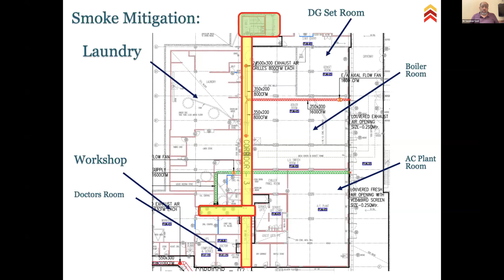Now, having said that, I will come back to the basement car park. So what we are talking about is smoke mitigation—please read this line. This is the line which helped me present to my committee: any kind of smoke mitigation system has to function in terms of ACPH when the fire is extinguished. The pressurization system works while the fire is occurring, so as to create a positive airflow so smoke does not enter the spaces being used by human beings for egress.